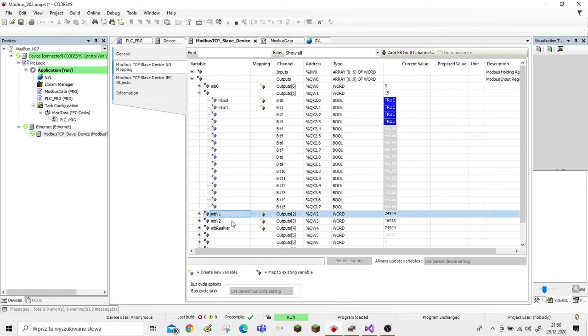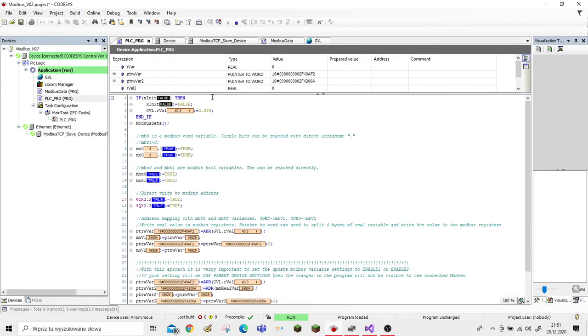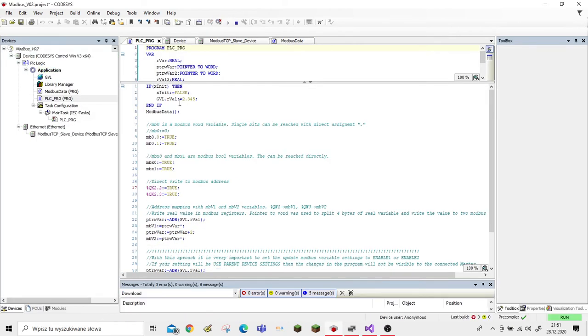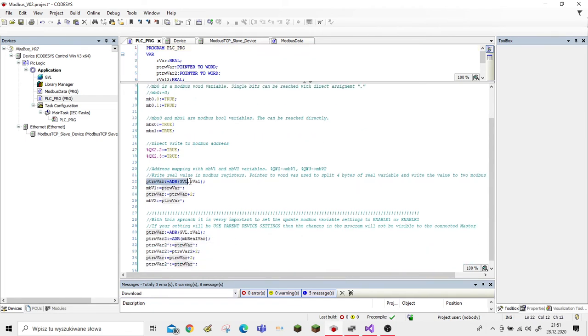Now let's have a closer look at how to send a REAL variable over Modbus protocol. In my case I'm using pointers, because we have to split the REAL variable into two words — REAL is four bytes and WORD is only two bytes. First, we assign the address of our REAL value to our pointer.